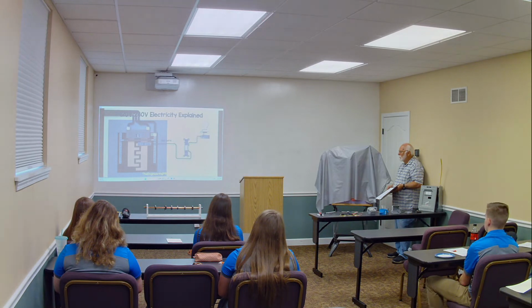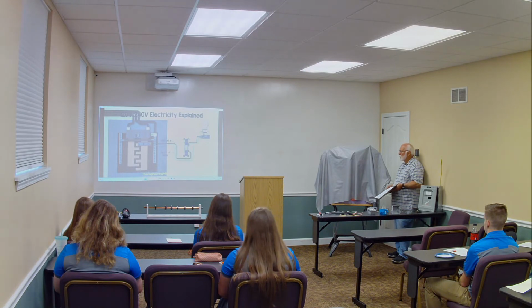We then run another wire from the switch and over to the light fitting. From the light fitting, we have a neutral wire which carries the return current back to the neutral bus bar. We take the ground wire from the metal casing of the ceiling box and the switch, and we also join this to the neutral bus bar, as in this case it's shared.